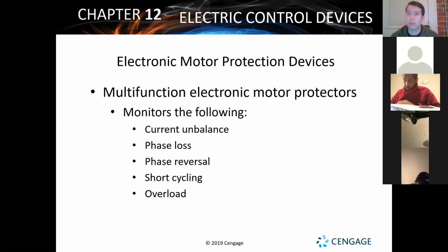So if we have it where one side of our motor, the windings, if the resistance changes, if it increases or decreases, that'll change the amperage on one side of our motor versus the other. And that will make it so that the motor actually rocks a little bit, because now the magnetism created by that amperage is uneven, and so the rotor inside is going to get pulled unevenly. And this is a very common thing you'll see.